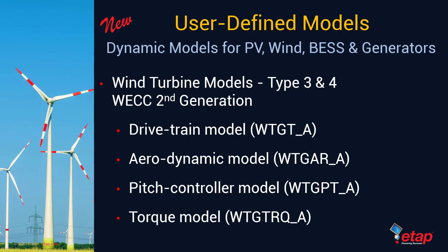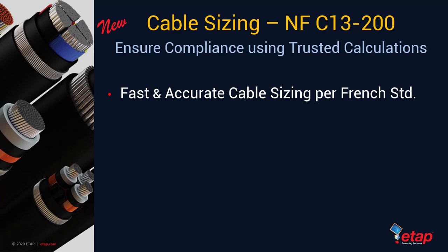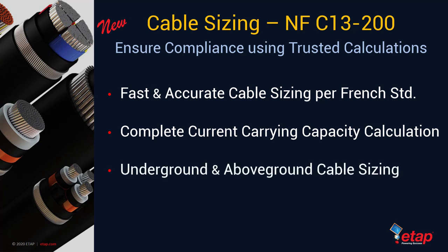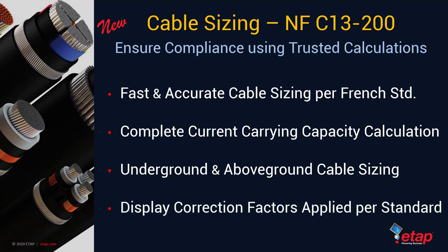Wind turbine models for Type 3 and Type 4 are based on WECC 2nd generation and have been added as part of ETAP20 release, including the drivetrain model, aerodynamic model, pitch controller model, and torque model for the wind turbines. We've also added a brand new cable sizing module in ETAP20 for fast and accurate cable sizing per French standard NFC 13-200. You can perform complete current carrying capacity calculation for underground and above ground cable sizing, and it allows you to display correction factors applied per the cable standard. On batch cable sizing, you can see all correction factors being applied to all conductors in a single tabular fashion, allowing you to produce a compliance table showing how cable sizing was performed and what derating factors were applied.